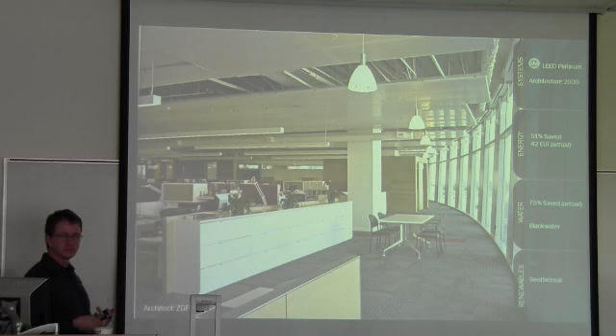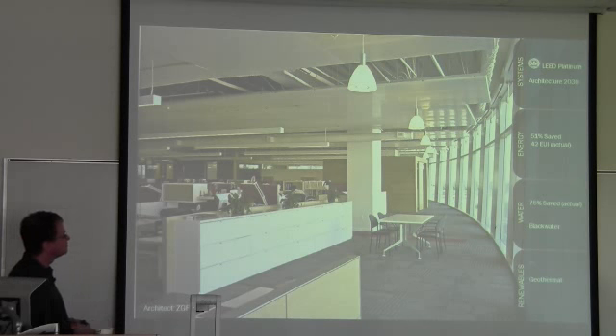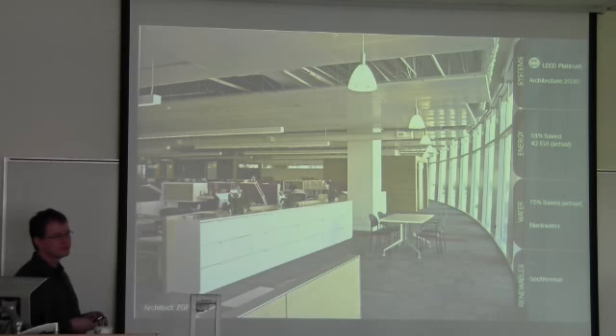There was an occupant survey done as a study here at the university that produced a report of what the satisfaction is for the space now after 2 years of operation. So this EUI 42 is an actual. If you look at it, it's a path to net zero, but it's not net zero. Net zero buildings that are producing their own energy need to be in the below 20 range. So this building did a lot of optimization to the skin, optimization of the delivery system for the heating and cooling to the space, but still, on a path to net zero, fell short.